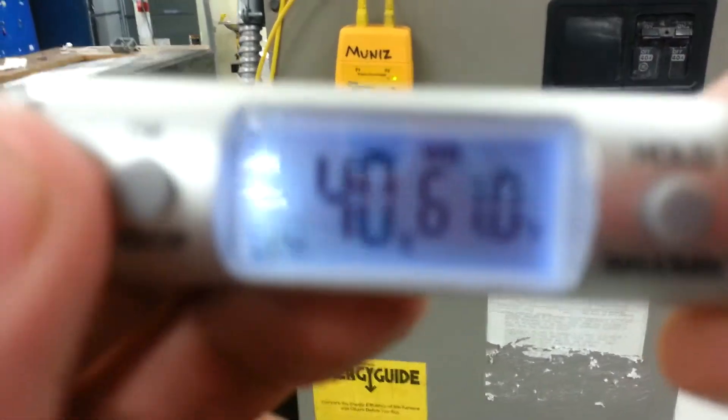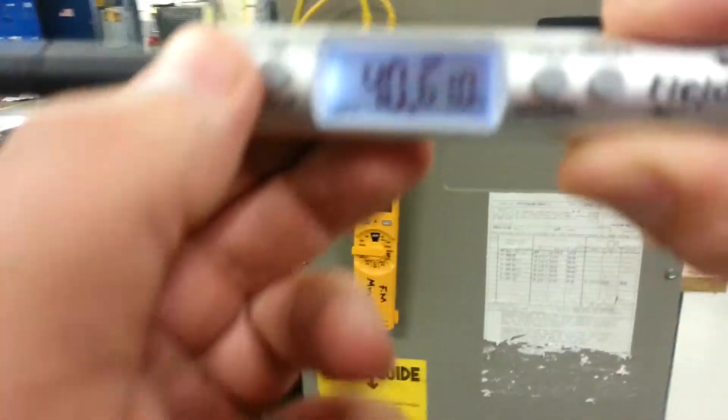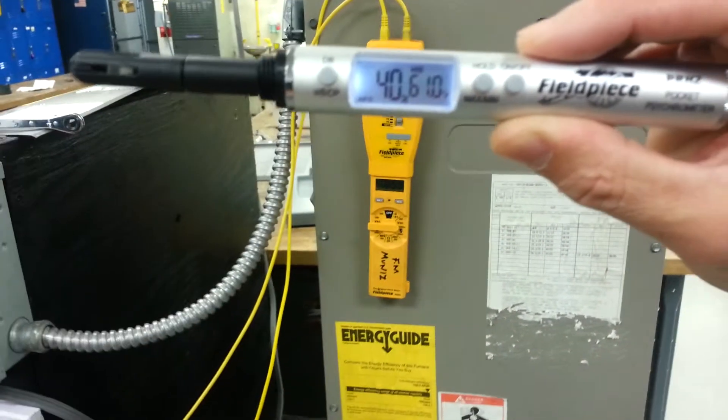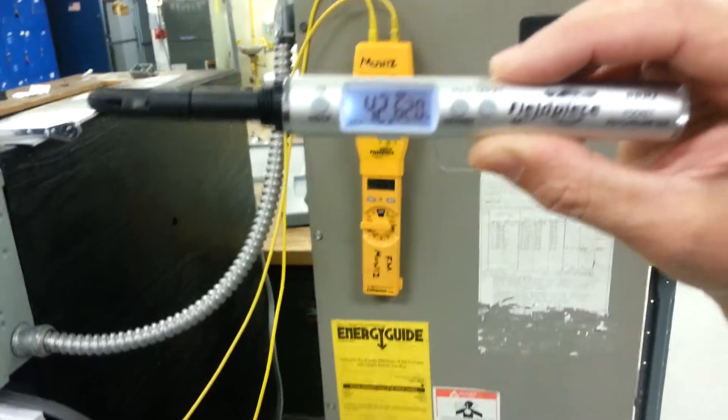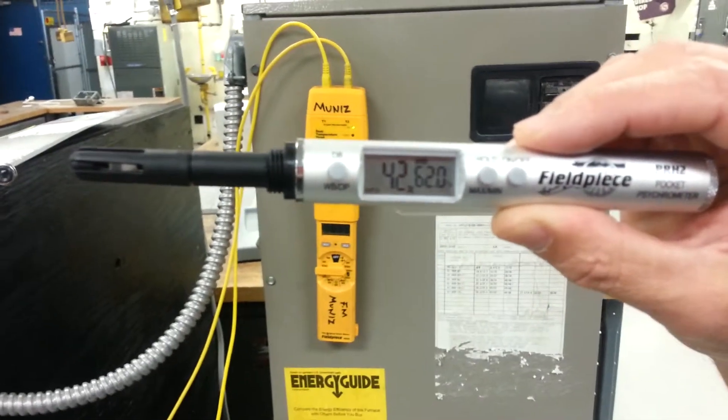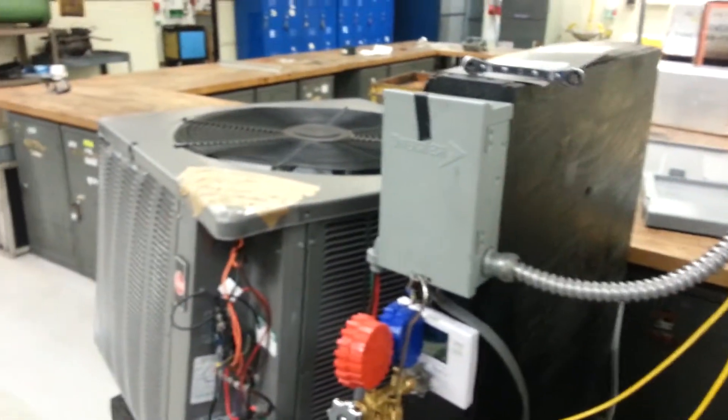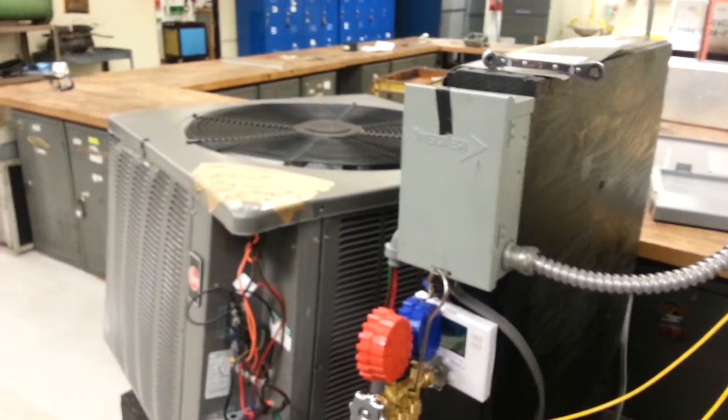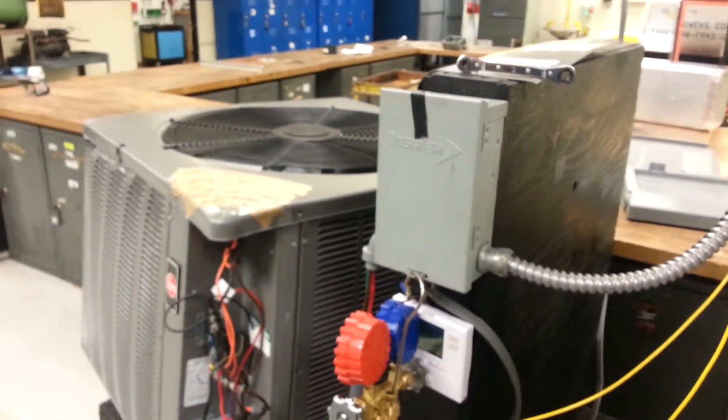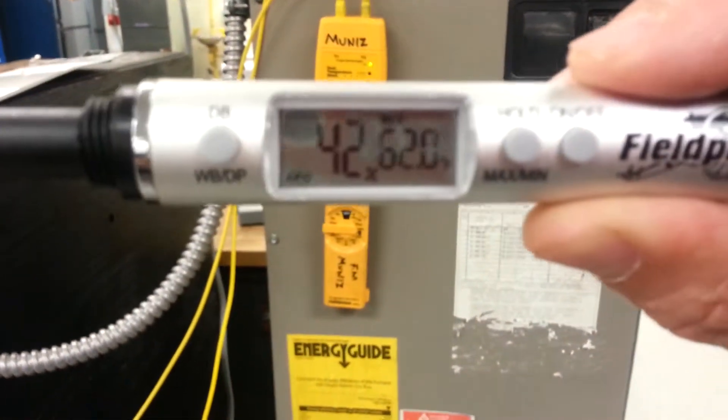See where it says 61 degrees indoor wet bulb. Alright, and then we're going to do the outside. The condenser's always outside, so it's going to be at 100 degrees. So 62 degrees indoor wet bulb.